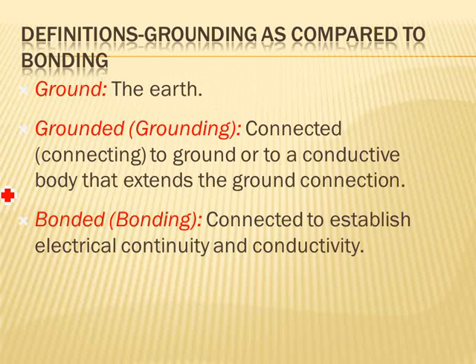One conductor can act as an equipment grounding conductor and a bonding conductor at the same time. Take an EMT conduit between two panels, 4-inch EMT conduit between two panels. The EMT conduit will act as an equipment grounding conductor, approved by code up to certain distances. Did you guys hear that there's a distance limitation? How far can you pull a 4-inch EMT conduit before it loses its ability, before the impedance increases? The code has a couple of tables at the end: a couple of hundred feet, then it becomes too high impedance, and then you have to pull an equipment grounding conductor. So it's interesting. Connecting to establish electrical continuity, that pipe acts as an equipment ground conductor, and at the same time, with the lock nuts, acts as bonding, bonding this enclosure to this enclosure.